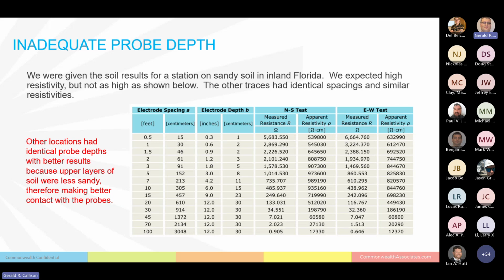So if there's one takeaway from both of these examples, it's to be cognizant of conditions that can impact the contact the probe makes with the surrounding soil. The meter just reads what it reads—it doesn't know if high resistance is from bad contact or if the soil is really that bad. It doesn't know if current is being picked up by a parallel pipeline, or if the soil is really that good. It's up to the people doing the grounding design and taking the measurements to make sure it's reading good information.